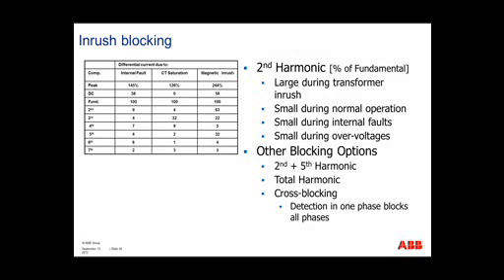So if we're looking at second harmonics, we can see that the percent second harmonics during a magnetic inrush is around 63%. However, for any internal faults or CT saturation, these components are very small compared to our magnetic inrush component. We also see that there is actually a large fifth harmonic component to this current. With that in mind, you can use the combination of both the second and fifth harmonic to identify your inrush condition and restrain from tripping.